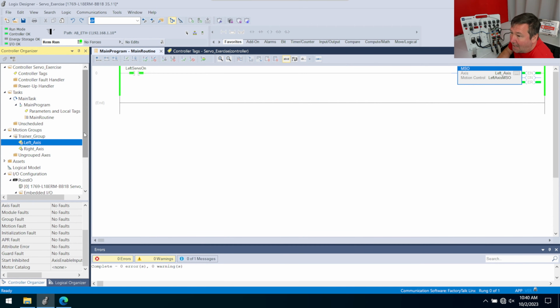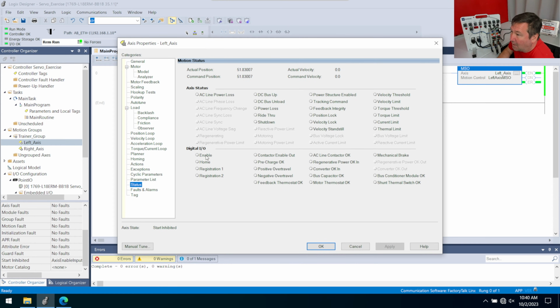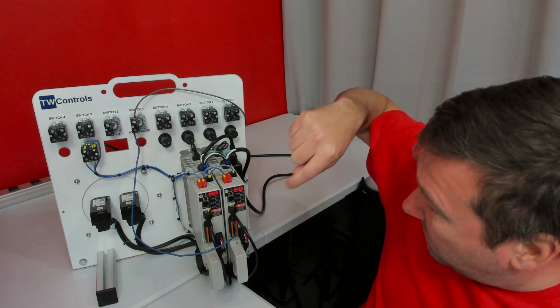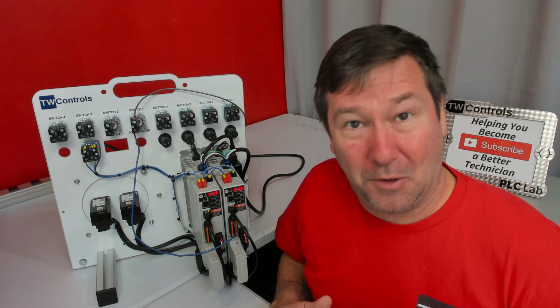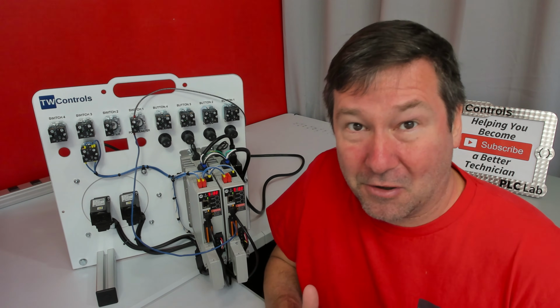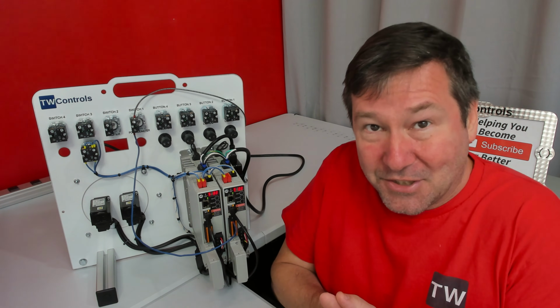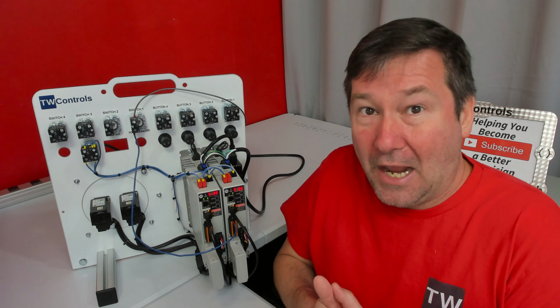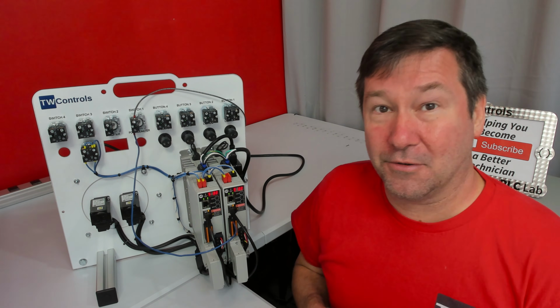And to see the value on that axis enable, we're going to go to our left axis and go to the status. And right there is our enable input. So as I switch one, I should see the enable turning on and off. And the issue is you have applied voltage to this terminal. But like I tell my technicians, they come to our class, in order for us to have action, whether that be an input or an output, we have to have current through the entire circuit.